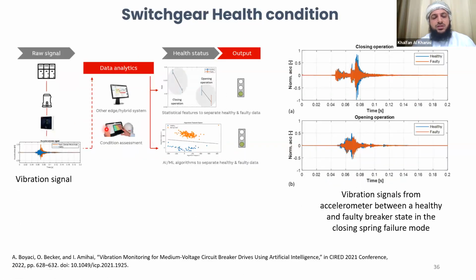Switchgear health condition: using vibration signals, we can identify the healthiness of the switchgear. This research focuses on vibration monitoring of medium voltage circuit breaker drives using artificial intelligence to detect whether a breaker is healthy or faulty.